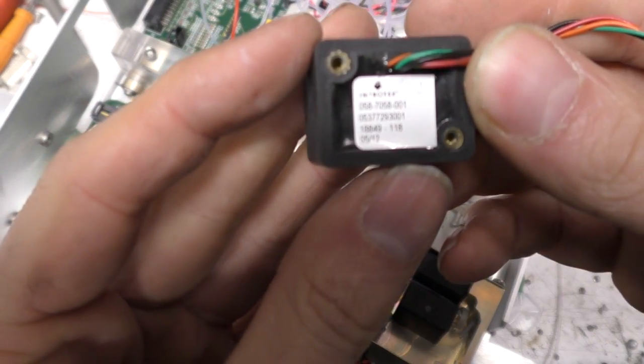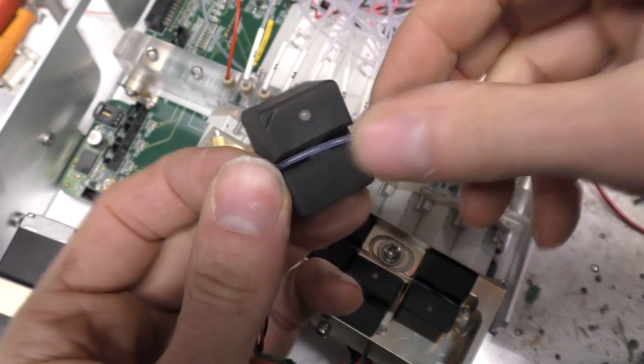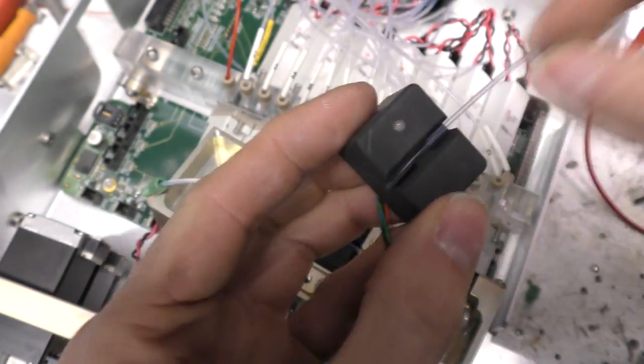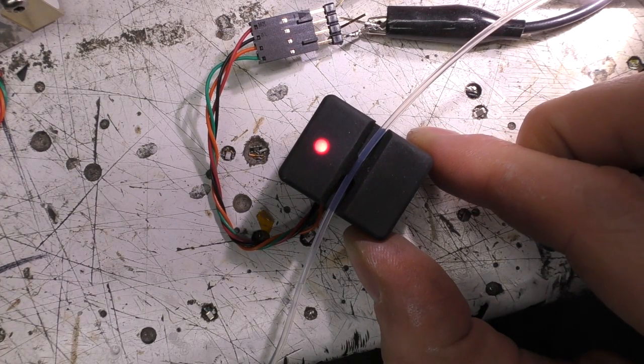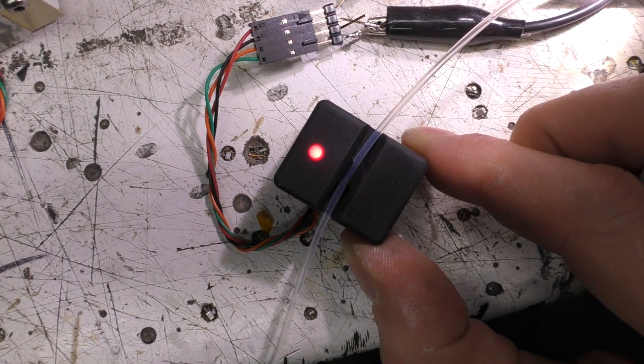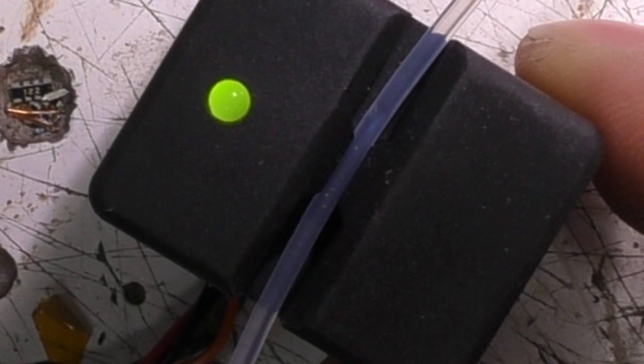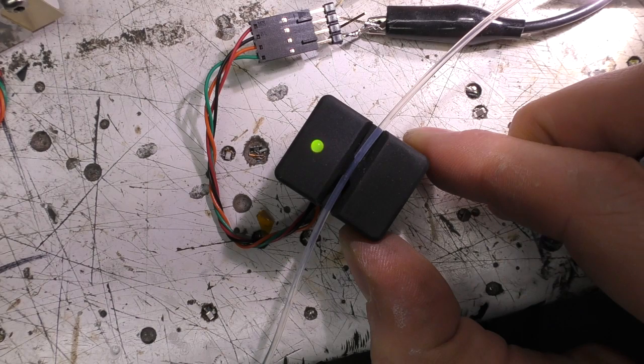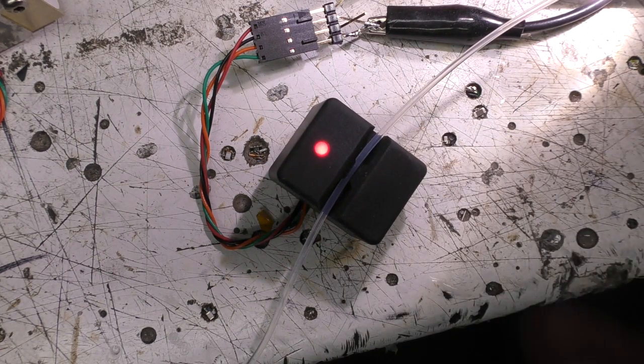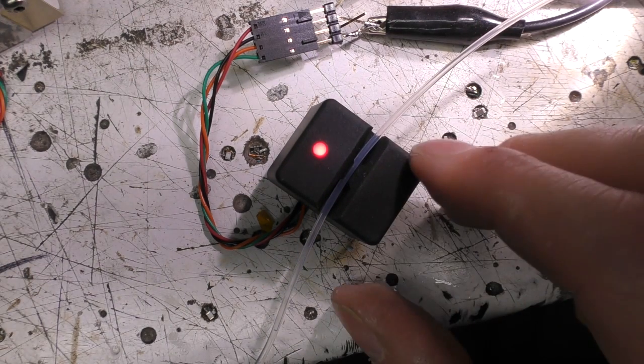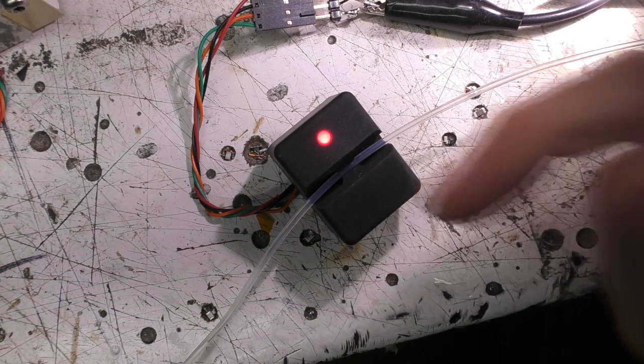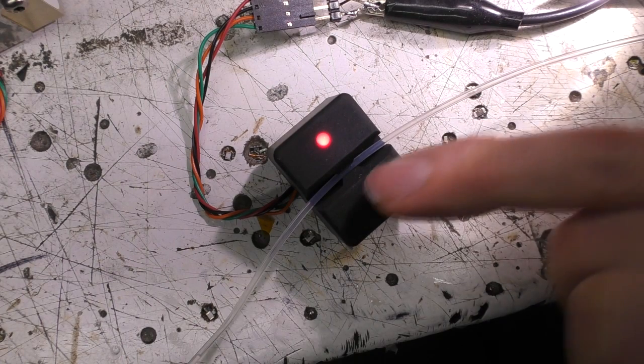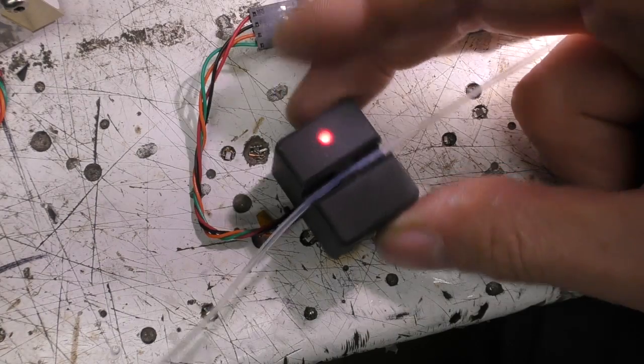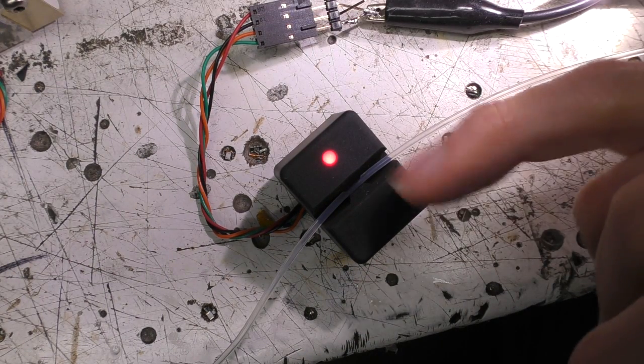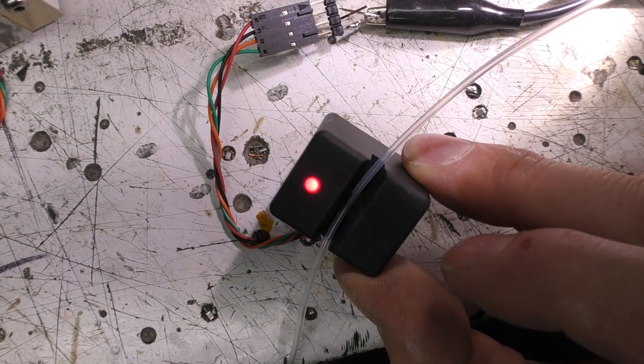Now, it turns out from the manufacturer name Introtek that these are bubble detectors. The idea is it uses ultrasonics to determine whether or not there's liquid in the tube that's passing through. You can see this is showing red when there's air in the gap, like a bubble in the tube, and if we put some fluid in the gap, it detects the presence. According to the website, these things are used quite often in medical equipment to make sure there are no air bubbles in various fluid lines. It's obviously just that the ultrasonic characteristics of an air gap are different to effectively a solid, because you've got these soft solid jaws touching the tube. Obviously the conduction through that is different when there's air in that gap.